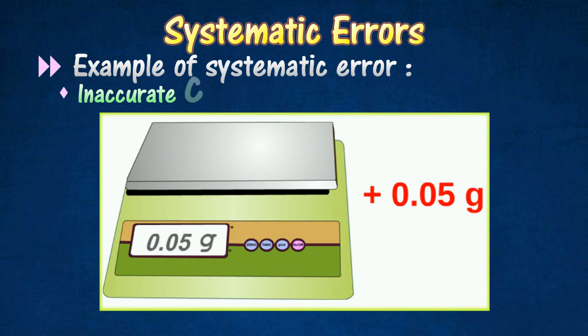First one is inaccurate calibration, which occurs for example if the electronic balance has been calibrated 0.05 gram too high. Then all the measurements of mass will give readings in excess of 0.05 gram.